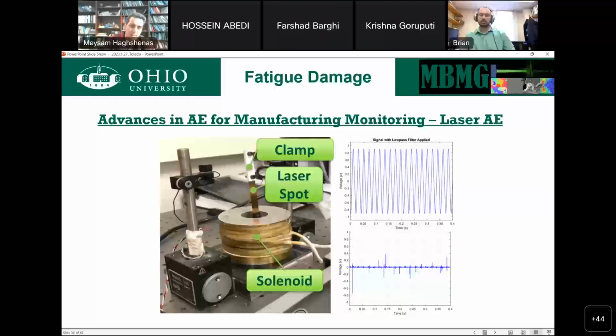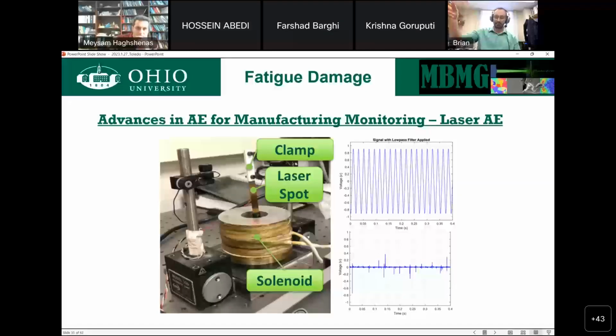The major limitation on acoustic emission comes from the fact we don't actually know the source. So a source happens, you have a damage initiation which releases energy that gets convoluted as it travels through the material, convoluted with the sensor itself, convoluted as it goes through. So what you're actually getting as a wave is not the source, it's the source plus all of these other things. So you have to find a way to back that out, which means to get useful information out of AE, it's really difficult to just stick something on there, get a result, and say that's what that is.